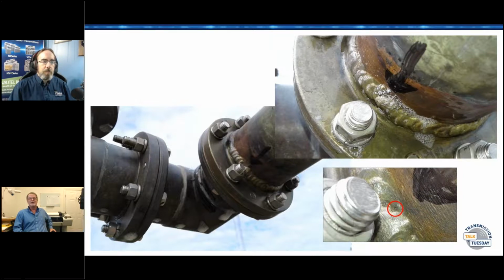Once I found that, I got my ultrasonic leak detector and took it out there, and it could hear the leak. But if you put your finger or anything over it, you wouldn't know it was there. It was actually dirty too — I had wiped this down before I sprayed it, and a little bit of dirt on top of that hole and you just don't know it's there. So everything I could reach without having to climb up the tower with full rigging gear, I sprayed and checked, and that was the only leak I found.